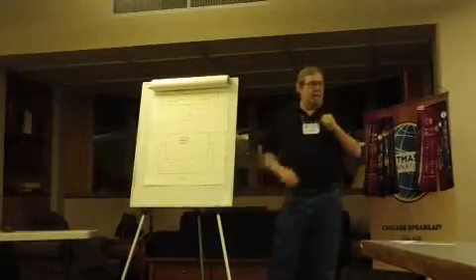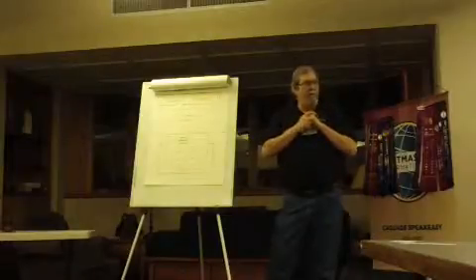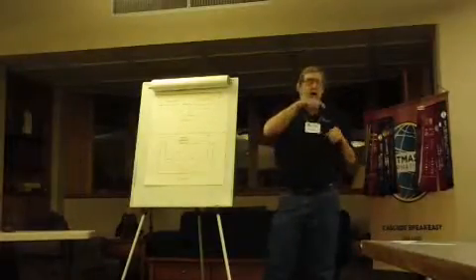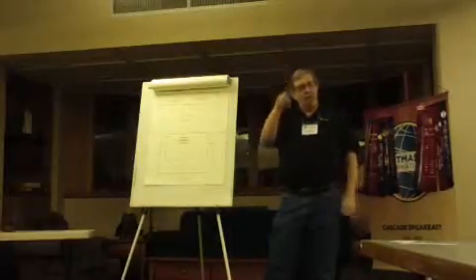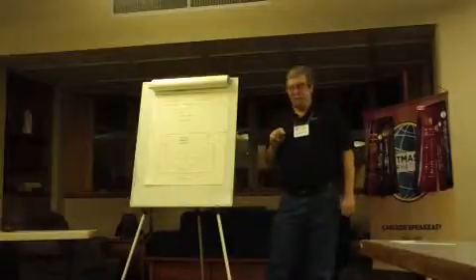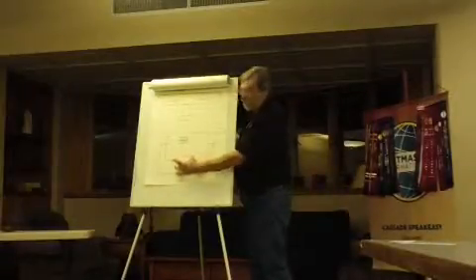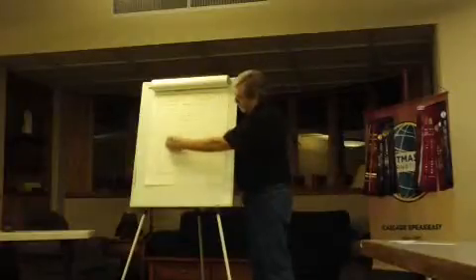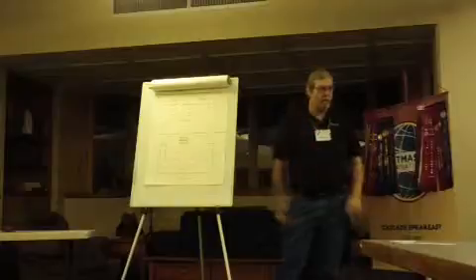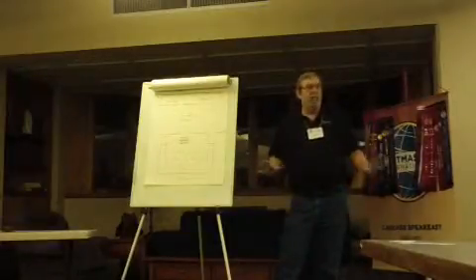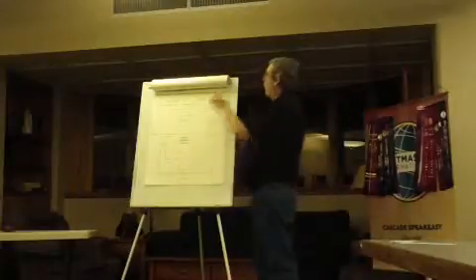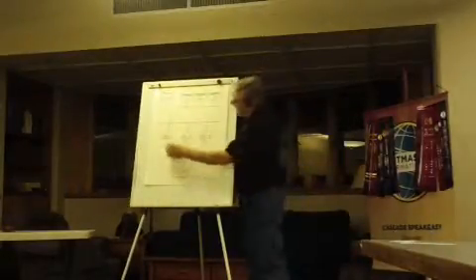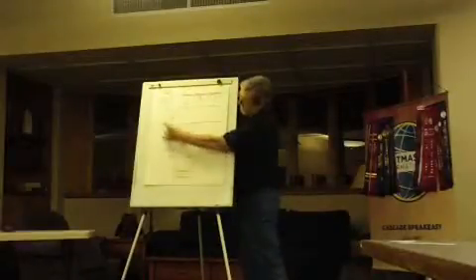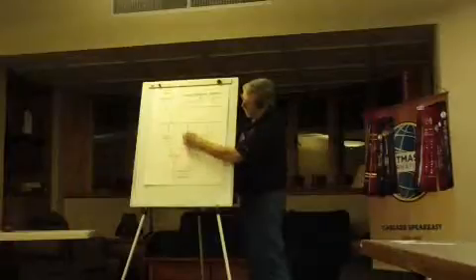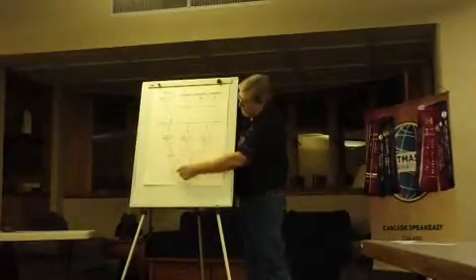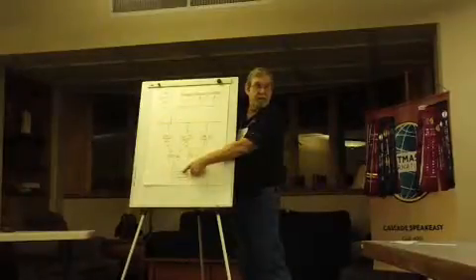In America, 60 cycles of power is what we have. In Europe, they use 50 cycles of power. That means that on a 120 volt circuit, it goes to a positive 120 to a negative 120, 60 times in a second. This thing switches, so it detects a problem upstream, and it will switch from source 1 to source 2 in one quarter of one of those wave cycles. That is so fast, the computer never sees it. And so that's how we get back to this. So if, like in this example, UPS-A decides to go bad, this thing's going to transfer over here to my redundant UPS so fast that this computer never saw it coming, and it stayed up and running.